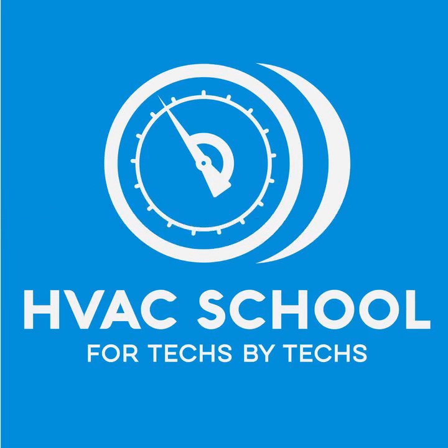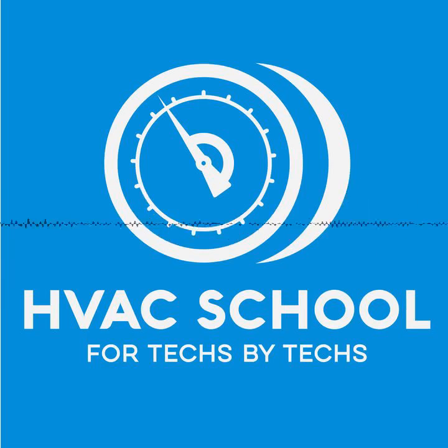If not, here's what I recommend you do. When you pull that valve out, and this is very important, rather than just replacing it, if it's got a removable orifice, pull that orifice out and look at the screen. If it's plugged, you have to ask yourself, why is it plugged? Where's my filter dryer? Why didn't the filter dryer pick up on this? It's an important question because if you just stick that TX valve back in there again, you've got to ask yourself, if that filter dryer didn't capture this debris, what's to say that there's not more of this stuff floating around that can possibly plug this?